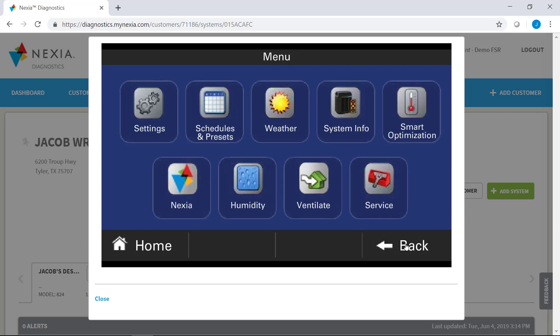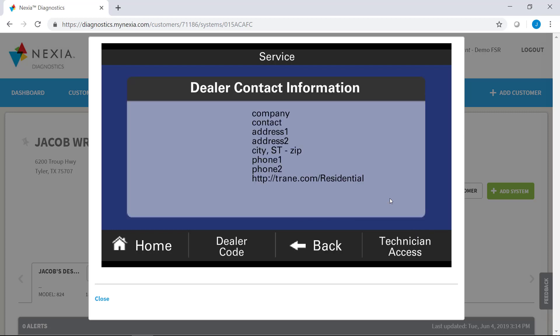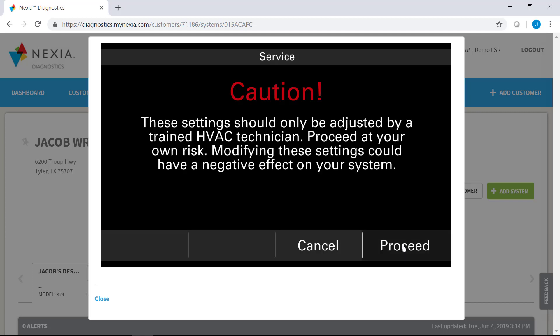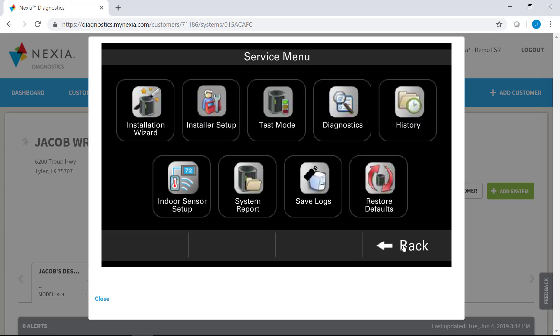So what about the serviceability? So you can easily get to the installer setup menus from the thermostat the same way you would get to it from a physical thermostat. You go to the service menu here and you'll hold down this technician access button just like you would at a thermostat. And it will take you into the menu where you're able to go into your installer setup and you can do indoor sensor setup or you can look at the diagnostics for the system itself.